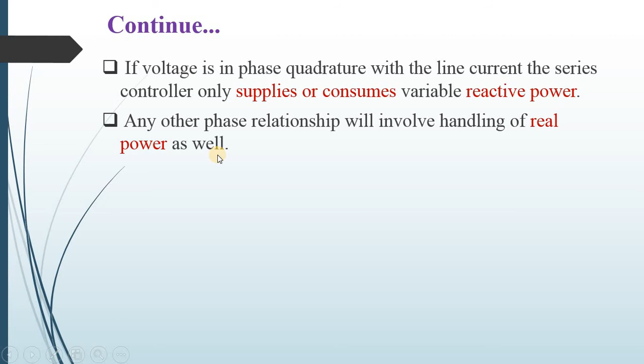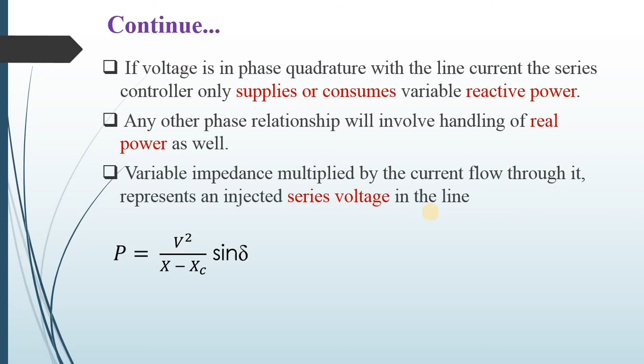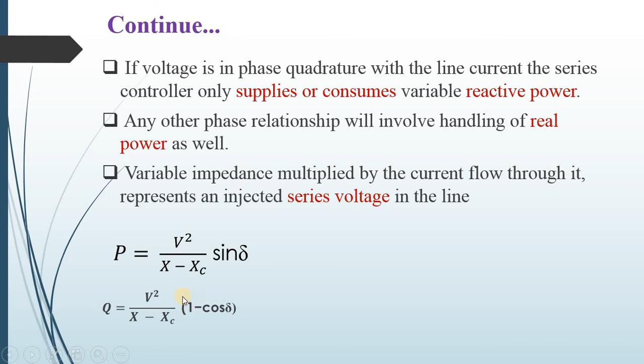Variable impedance multiplied by the current flow through it represents an injected series voltage in the line. In this way, it injects series voltage in this line. The formula for active power in case of a series controller is P equals V squared upon X minus Xc, times sin del, where X is the reactance of the transmission line and Xc is the reactance of the controller. Reactive power is V squared upon X minus Xc, times 1 minus cos del.